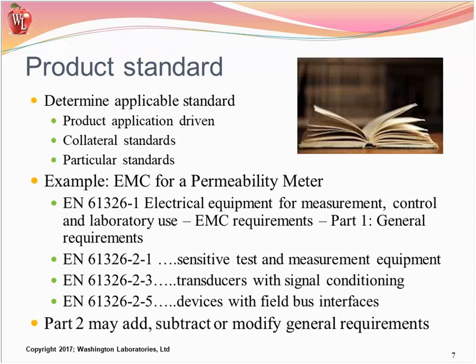For example, in a medical device, you may have an alarm system, so the alarm system collateral standard would also apply to the product. Software and things that make the essential performance happen need to be associated with it and may need to be approved.